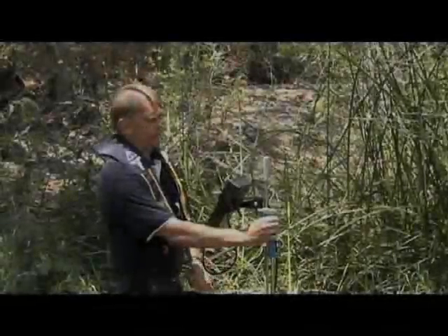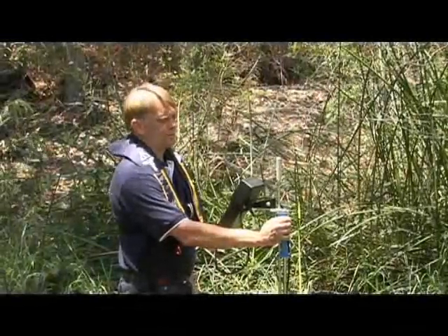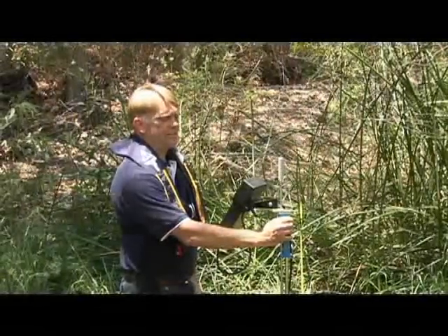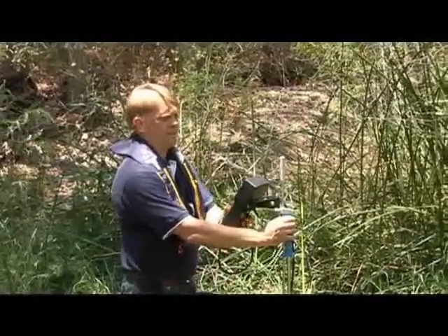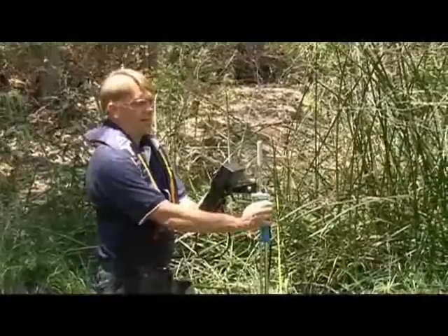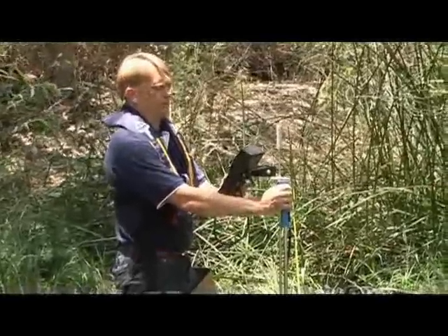Okay, so now my measurement's complete. My velocity reading was 0.026. The variation of velocity was 1,000th of a meter per second. The angle was 3 degrees. The SNR was 16.5. Spikes were 0 and the boundary was best, so I'll accept.